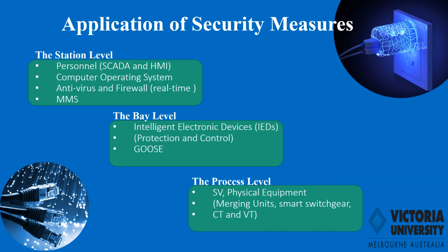There are simple security measures and techniques that can be implemented inside a substation environment. For instance, personnel working at the station level must be knowledgeable in computers and know the substation process. The personnel working on SCADA and HMI must be properly oriented and must abide by the security policy of the organization. The inclusion of a graphical user interface for measures like biometrics and others will make computer access more protected. On the side of the operating system, the Control-Alt-Delete key combination is called a secure attention key.